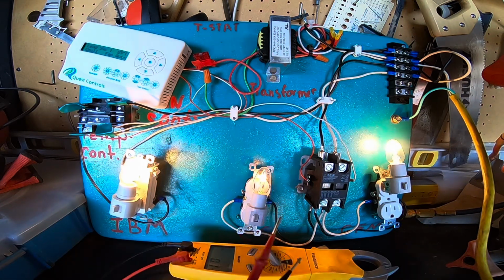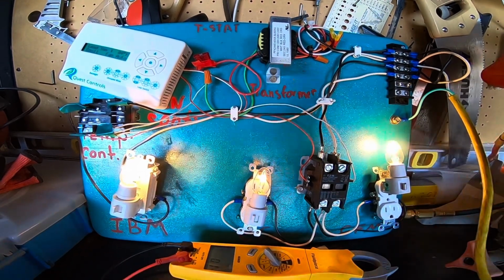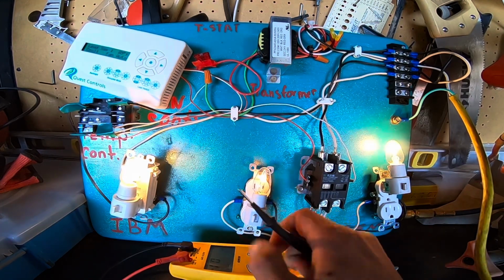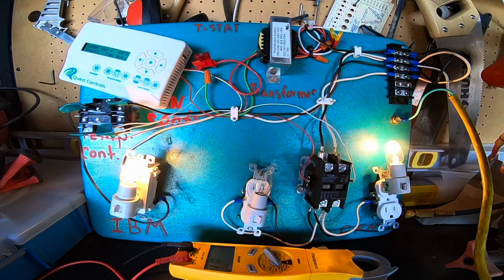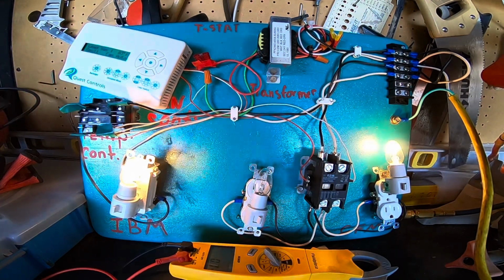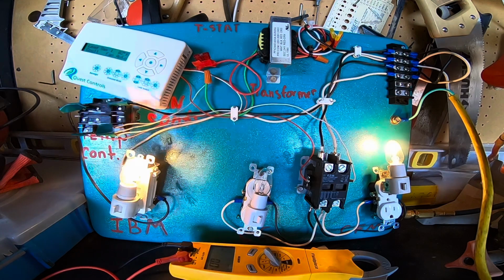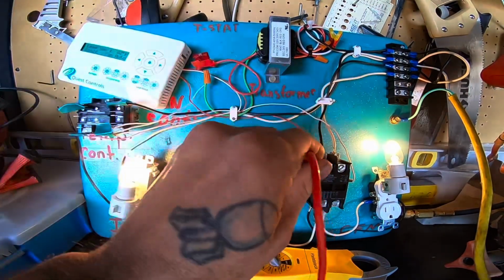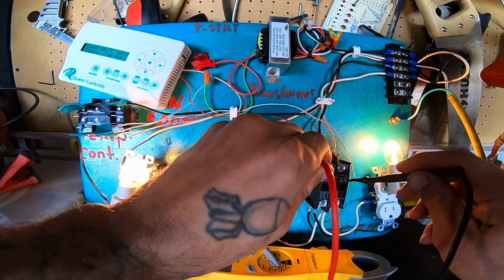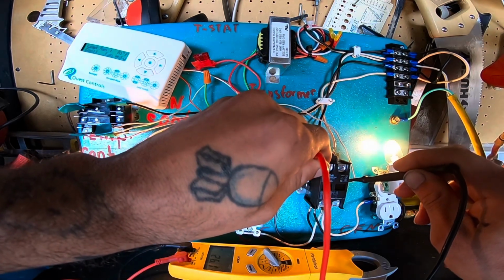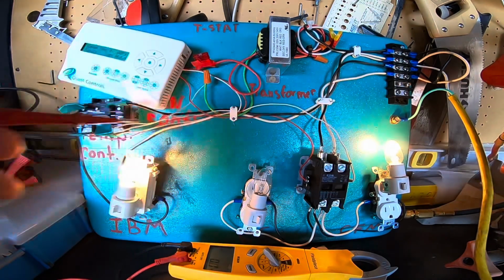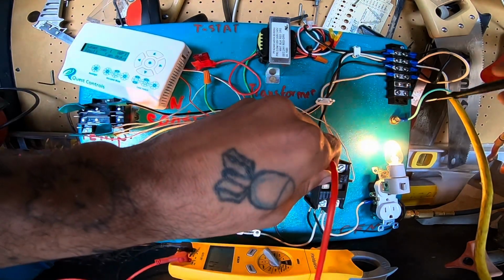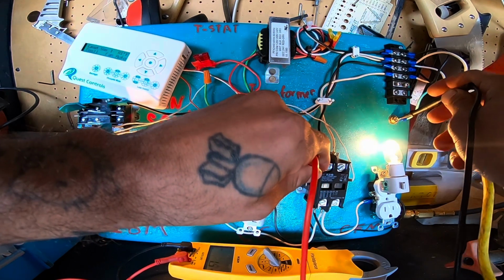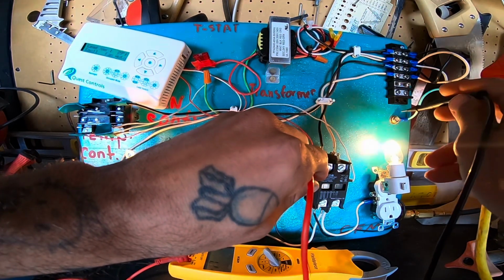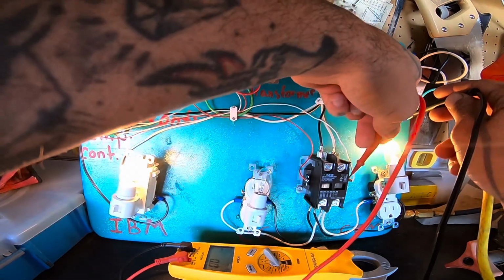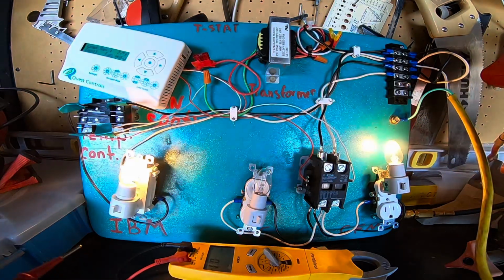So typically, what I see a lot of people doing, let's say, okay, this is our compressor, let's turn it off. Okay, compressor's not running. What's your process of elimination? Well, you always start at the controller and make sure that the controller is calling for cool. And then typically you'd come to the coil and check power at the coil, which I have 26 volts. I see a lot of people doing this. They go to the coil and they'll check power to ground, right? And then if you have your common wire to your ground, essentially when you check power to ground, you're going to see 24 volts on each side of the coil. So that can be kind of confusing when you're troubleshooting.